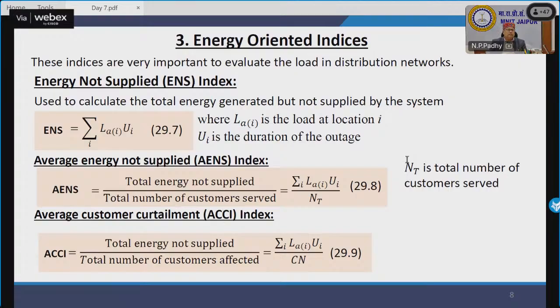Now, what is average energy not supplied? AENS is the total energy not supplied upon the total number of customers served. That is summation of LaiUi upon NT. NT is total number of customers served. Now, average customer curtailment, that is ACCI index. ACCI is equal to total energy not supplied upon total number of customers affected, which is equal to summation of LaiUi upon CN.